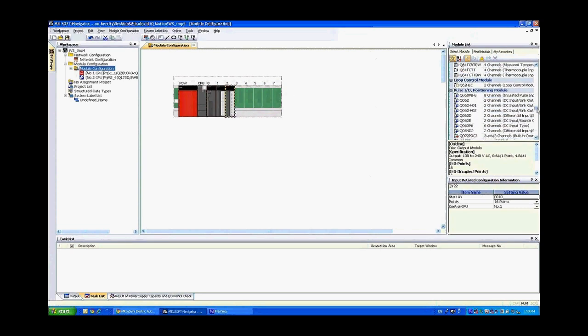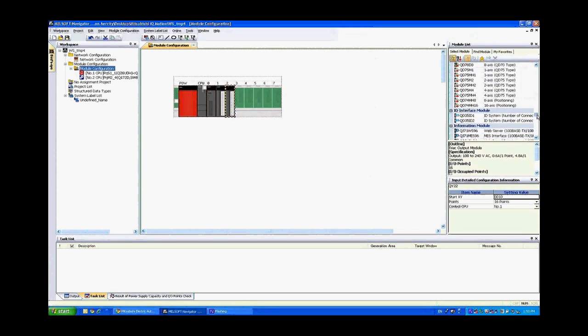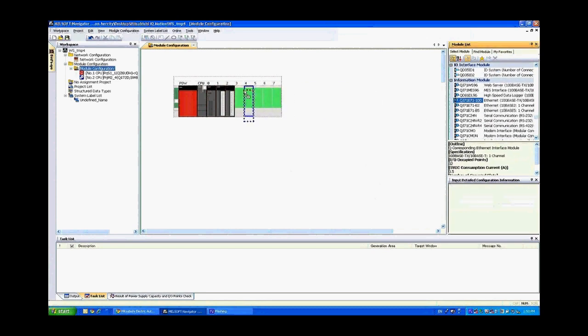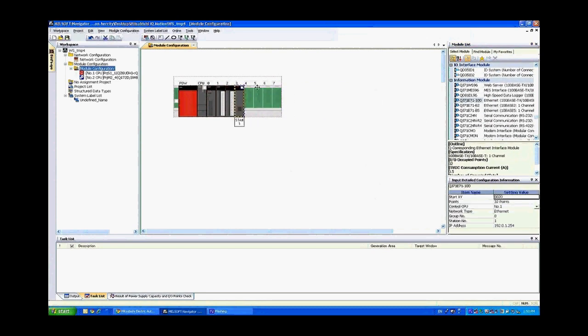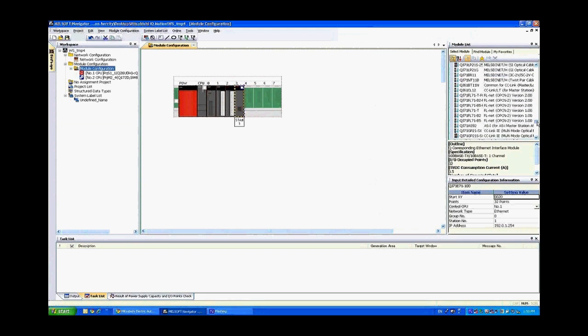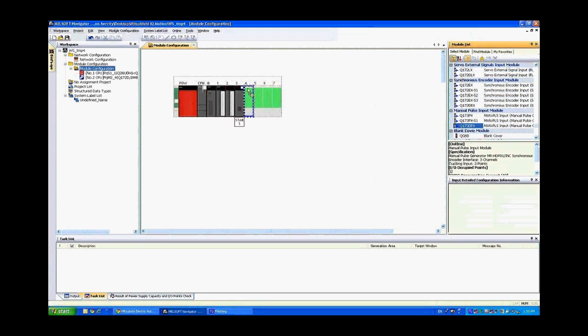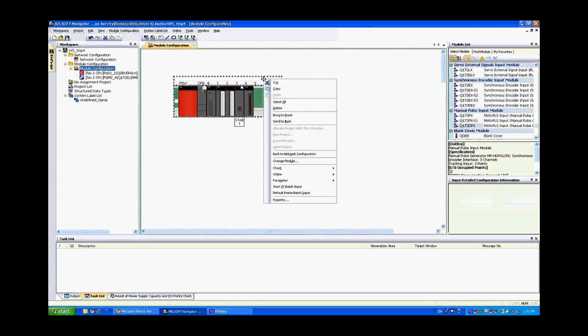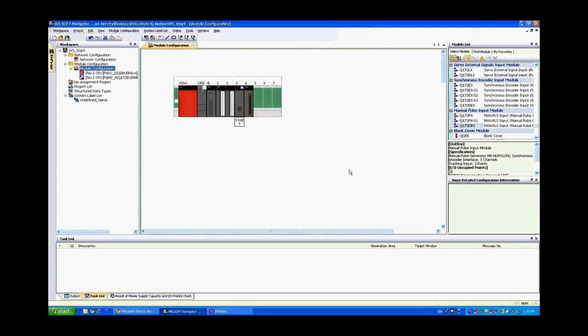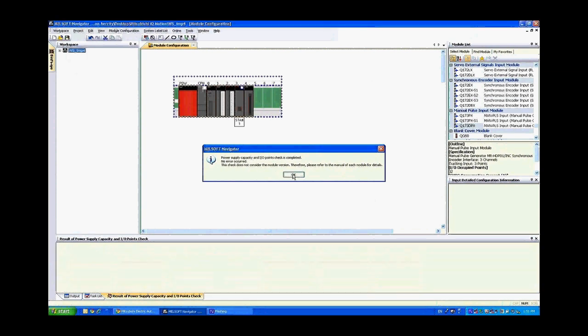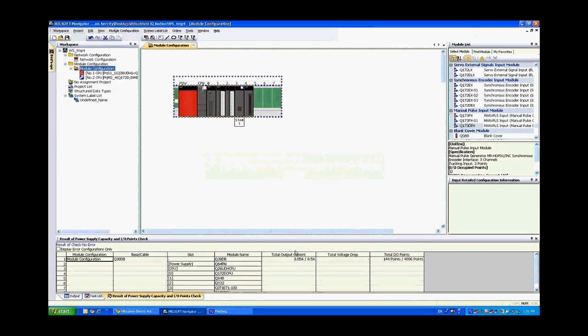Then we want the QJ71E71-100 and again this has to match the setup that you have on your desk as well. Then finally we'll drag over the Q173DPX card. Now next what we can do is right click on the back plane, go down to do a check and check the power supply capacity. This will tell us that the check has completed and no error occurred. Down at the bottom you can see that we're only consuming 3.05 amps out of the total 8.5 amps available from the power supply.